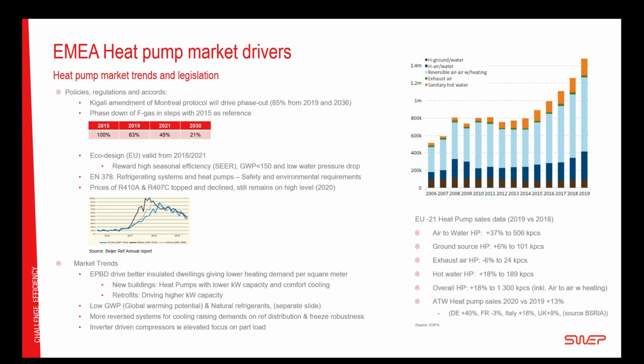Eco design here in Europe is driving the high seasonal efficiency, and also rewarding it: if you have a refrigerant below 150 global warming potential, you get very big benefits when you do your ratings. The low water pressure drop requirement has also been increasing more and more in recent years, and it affects us when we develop our new brazed plate products.